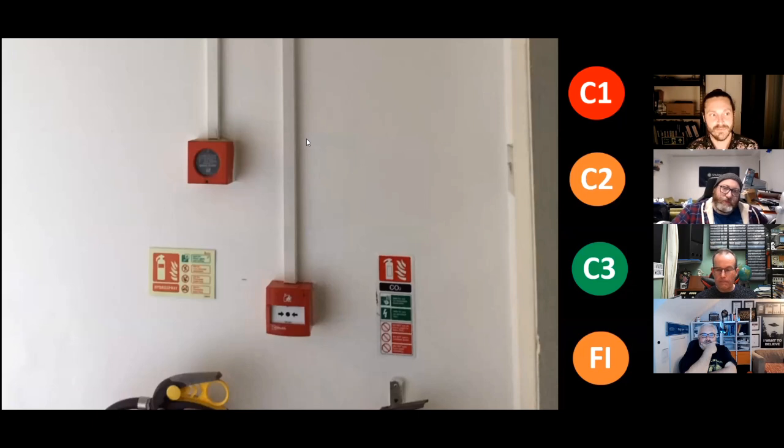That's interesting. I look at that and I immediately go, new system put in for the new Part M accessible heights for accessible persons, vulnerable persons, etc. It's a hybrid of new and old, but I still see plastic trunking, which I'm not a fan of. Personally, you know me, Dan, I prefer conduit systems every time, especially if it's a commercial application. The old one, I'm assuming, needs to be ripped out. If the two are running consecutively, I would suggest that somebody is being really cheap as far as fire alarm budgets go.